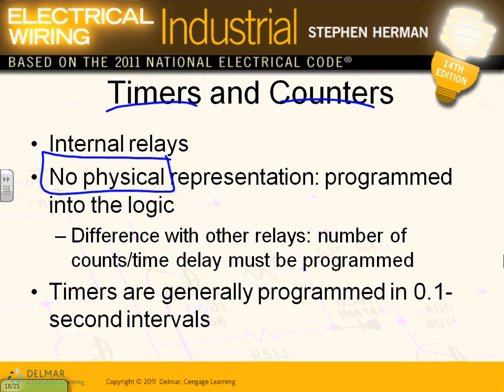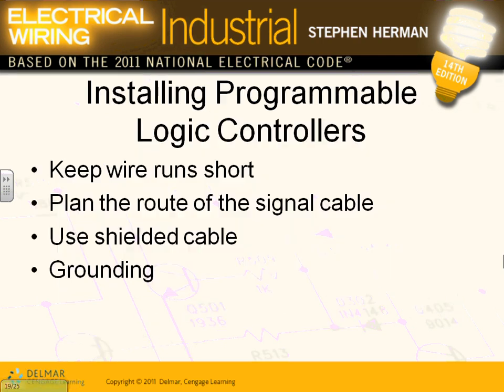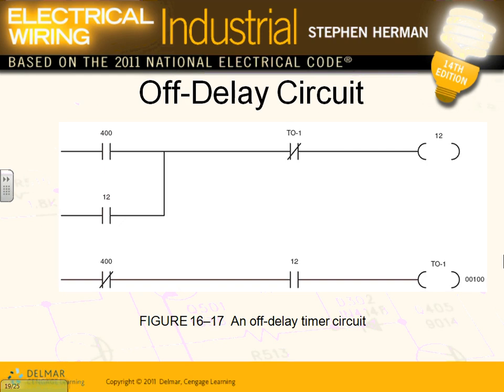Okay, so all these guys, the programming, logic, timers, and when we put in timers, guys, they have a 0.1 second interval. So that's one tenth of a second interval, so I can have 100 one-tenth-of-a-second counts and program it for 10 seconds. So really cool. You get all your timers and your counters, virtual timers and counters. No need for actual physical mechanical driven coil timers and counters. So these are an example of timers and counters. We'll get into that one in a second here.